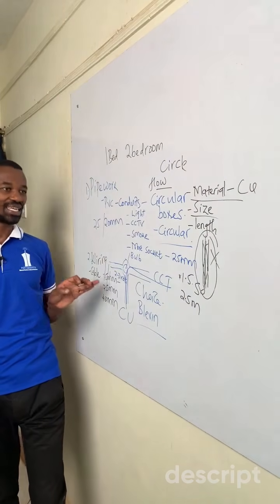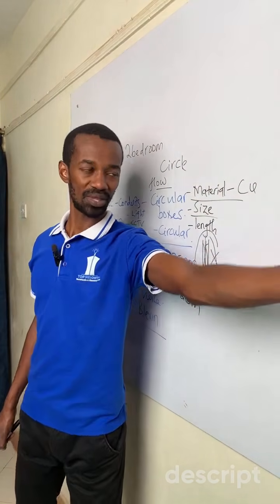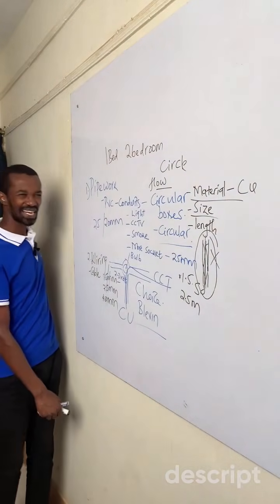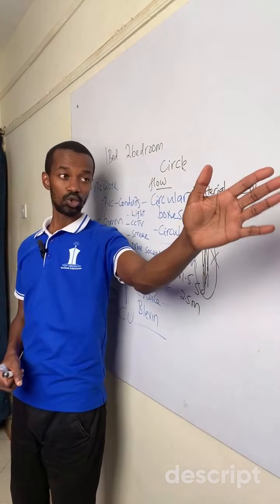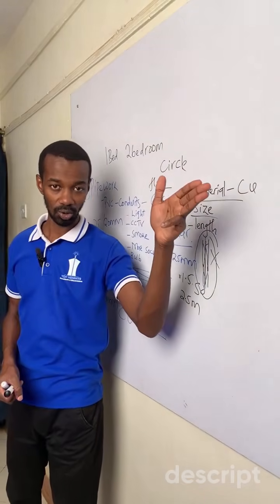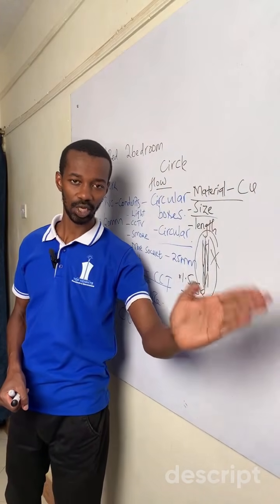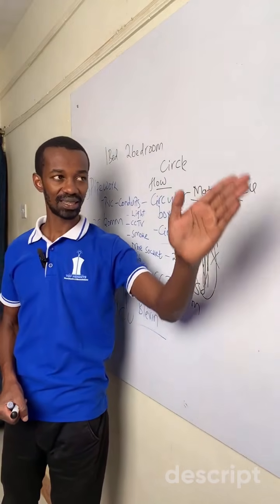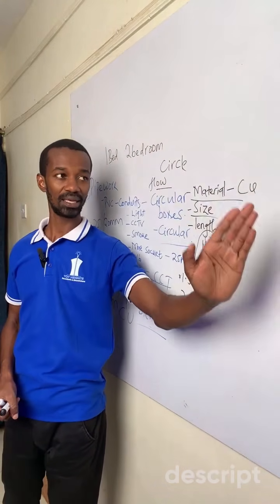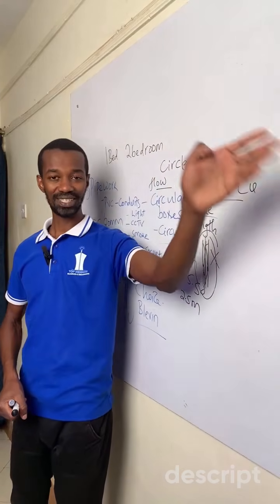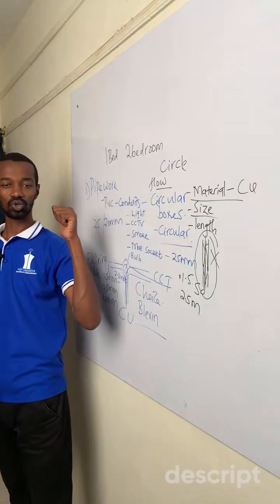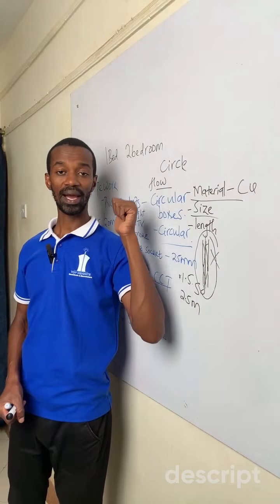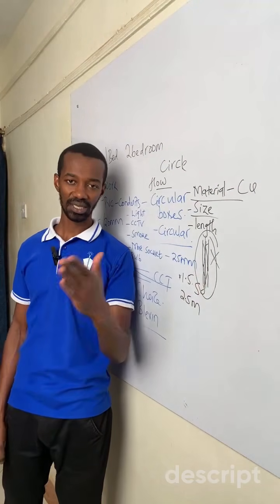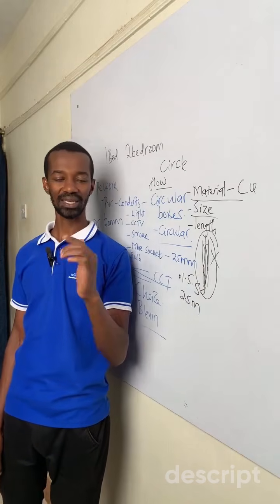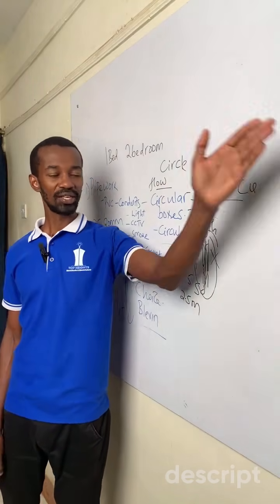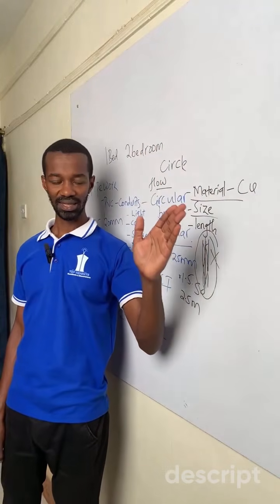But all in all, it will only be a single neutral dropping to that switch, another single neutral dropping to this. Remember, when connecting two-way switches, you require 2 red cables connecting both L1 as well as L2. When it comes to activating the common switch, whereby you require the common line from the switch to the consumer unit, a red is involved. From the switch going to the bulb, you also require a red. That is at least according to the standards that we have here in Kenya, which also apply in the UK, if I'm not wrong. Now, a neutral may not be used in that situation.